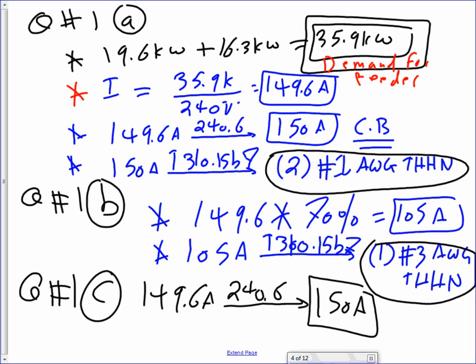We sized the feeder. Now, I'm not asking you to size the conduit for it, guys, but you can go ahead and size the conduit if you want to. I did not ask on the test to size the conduit. So this would be my circuit breaker. The circuit breaker is going to be 150.